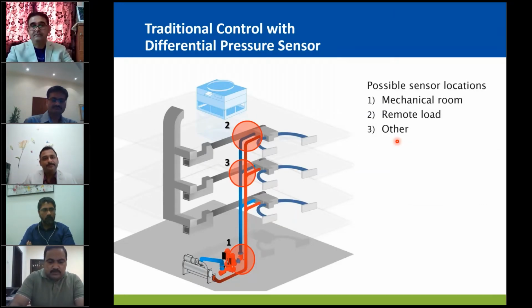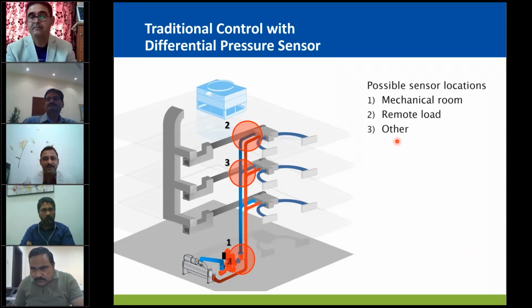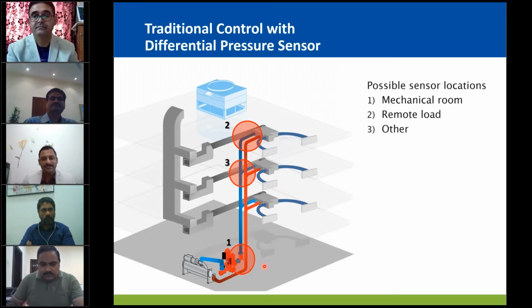Now, looking at traditional pressure sensors, how or where they can be placed. Today, we walk into the mechanical room, we find the sensors installed in the plant room most of the time, which is number 1 at the bottom, just close to the pumps, just because it's easy to install in the plant room. The second place and the best practice as per ASHRAE recommendation is remote load, or 2/3 of the farthest loop.